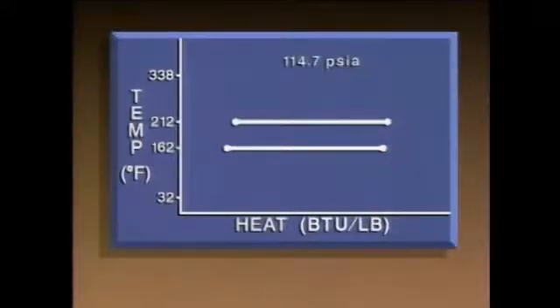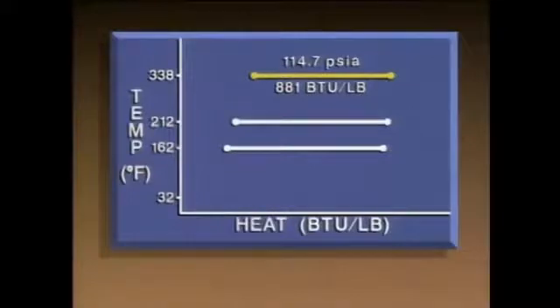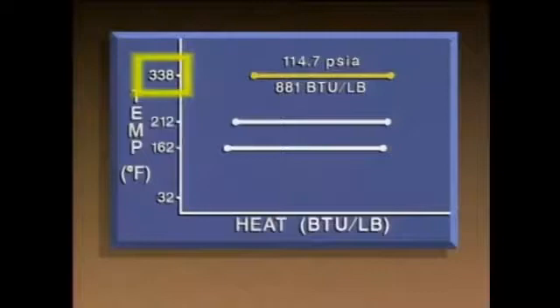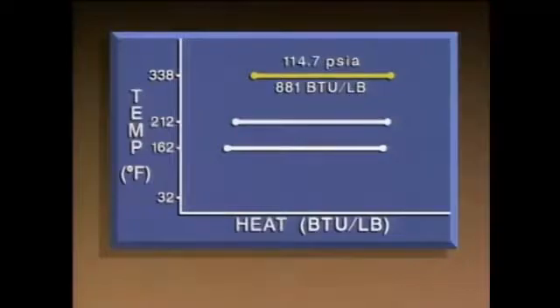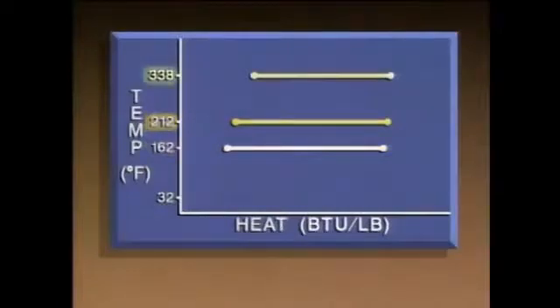Now let's look at a pressure higher than atmospheric. At 114.7 PSIA, water won't boil until it reaches 338 degrees Fahrenheit. Under these conditions, the latent heat of vaporization is about 881 BTUs per pound — less than at atmospheric pressure. At higher temperatures, water molecules move more quickly, so it's easier for them to escape as steam. In other words, it takes less heat to change the water completely to steam. As the pressure and boiling temperature of water increase, the latent heat of vaporization decreases.